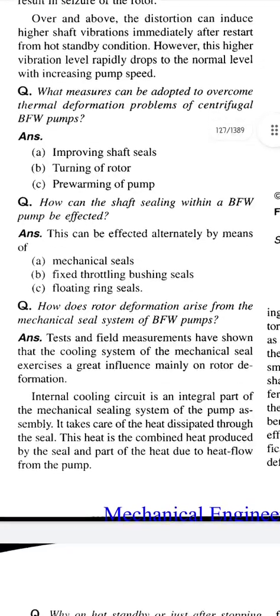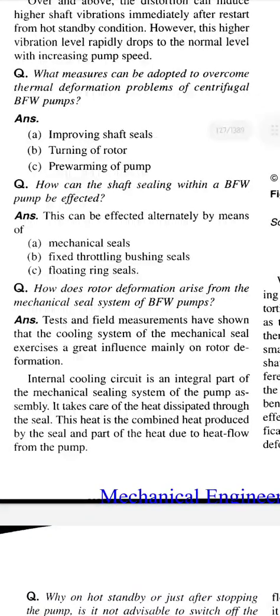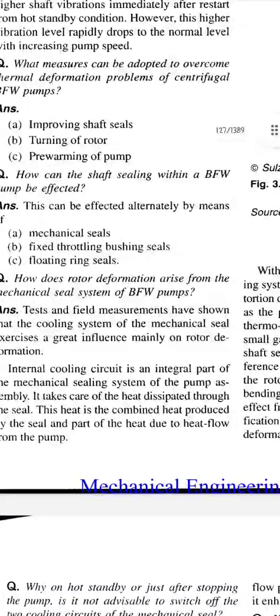Question: how does rotor deformation arise from the mechanical seal system of boiler feed water pumps? Answer: tests and field measurements have shown that the cooling system of the mechanical seal exercises a great influence, mainly on rotor deformation. The internal cooling circuit is an integral part of the mechanical sealing system of the pump assembly. It takes care of the heat dissipating through the seal. This heat is the combined heat produced by the seal and part of the heat due to heat flow from the pump.